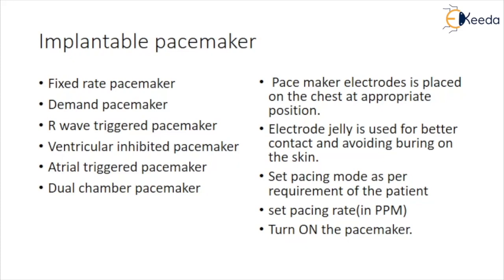The ventricular-synchronized demand-type R-wave-triggered pacemaker is meant for patients who are generally in heart block with occasional sinus rhythm. The pacemaker detects ventricular activity and stimulates the ventricles after a very short delay of about 30 milliseconds. If there is a sinus rhythm, the stimulating impulse will occur during ventricular depolarization — there is a systole. Otherwise, the unit will stimulate the heart after a preset time.